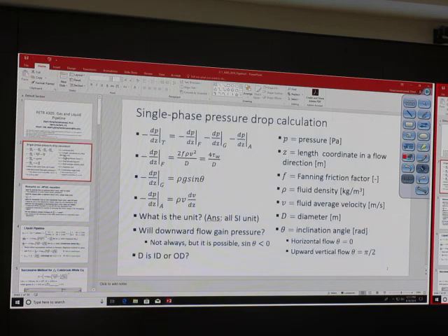Okay, this kind of piping, you've got to know how to calculate pressure drop for a liquid line. Pressure drop for the liquid line has two cases, laminar or turbulent. If it is laminar, you've got to use the right equation. Use 2f rho v squared over d, where f is the Fanning friction factor. You've got to write all this formula in, okay? 2f rho v squared, rho g sine theta. When we go up, we lose pressure due to gravity too. When we go down for single phase flow, we gain pressure due to the hydrostatic head.